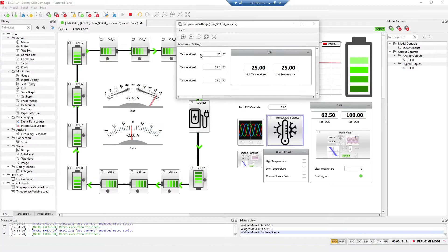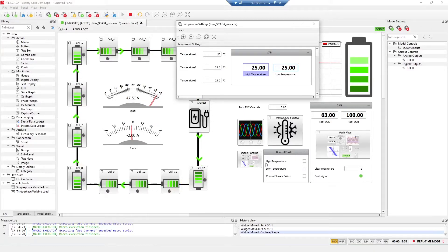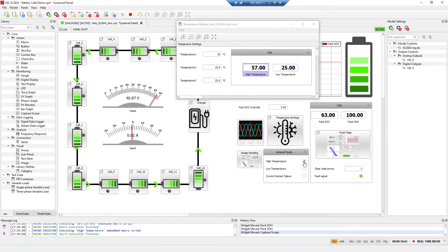In the temperature settings you can set temperatures and monitor through CAN what the high and low temperatures are. If I check here the high temperature from this group of general faults and set the high temperature to be 57 degrees Celsius, then the high temperature that the BMS is detecting is also 57 degrees. I will uncheck it now.